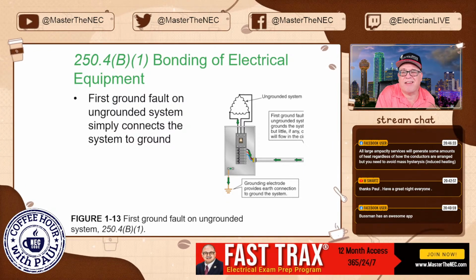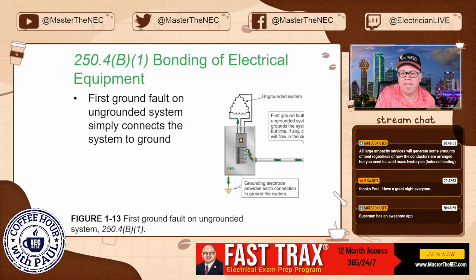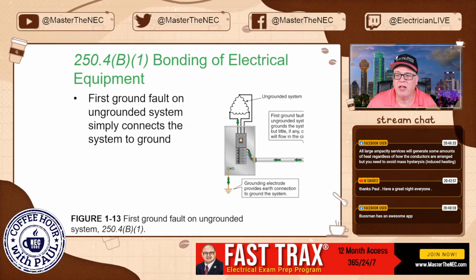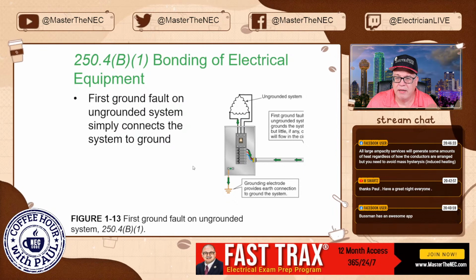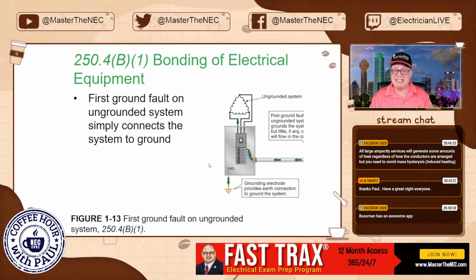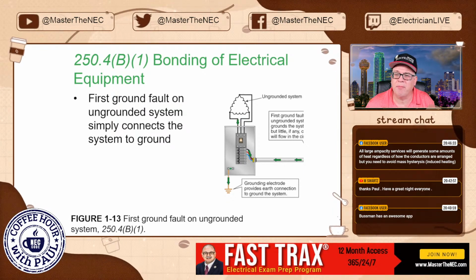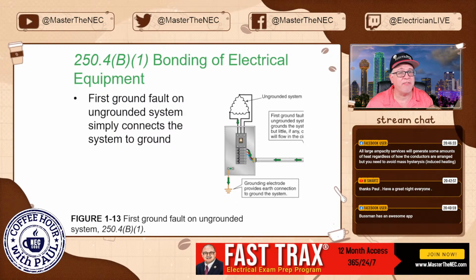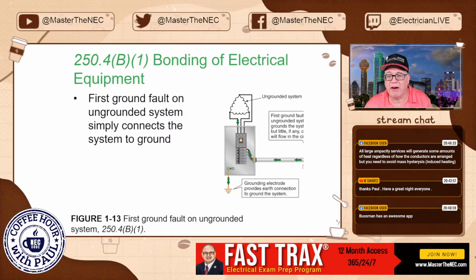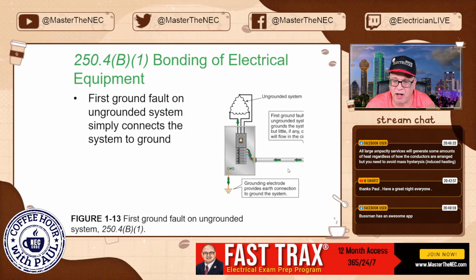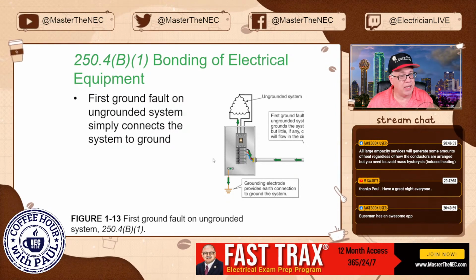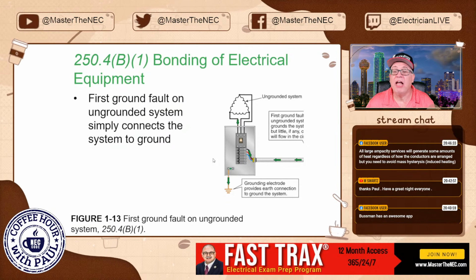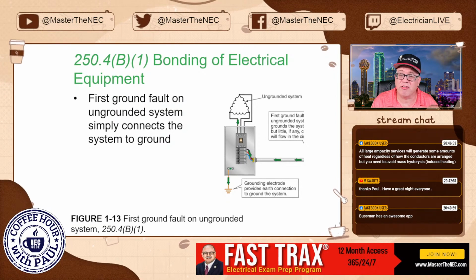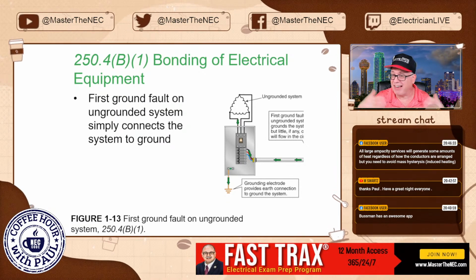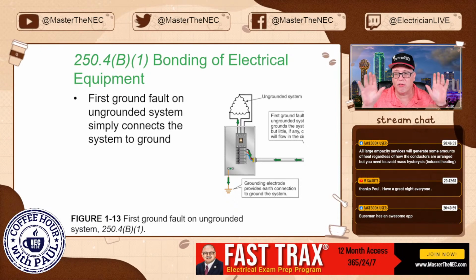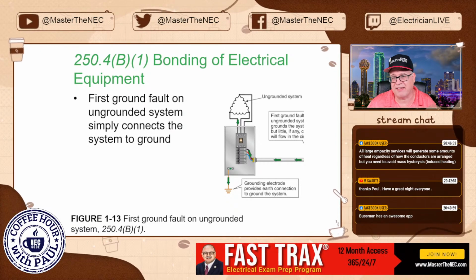It creates and establishes a ground, okay? And if any current will flow on that circuit. To clear the overcurrent device in an ungrounded system, at some point you're going to have another phase fault out to the raceway or fault out to the other phase, okay, in order to clear an overcurrent device. This is why systems like this that are ungrounded systems will generally have lighting and monitoring or an alarm type of systems and things like that.